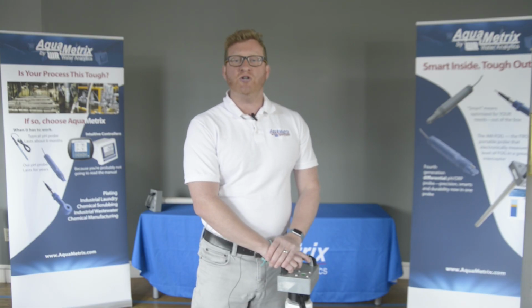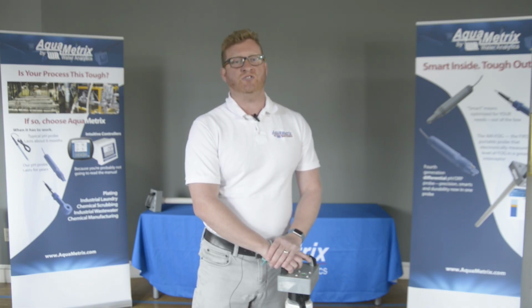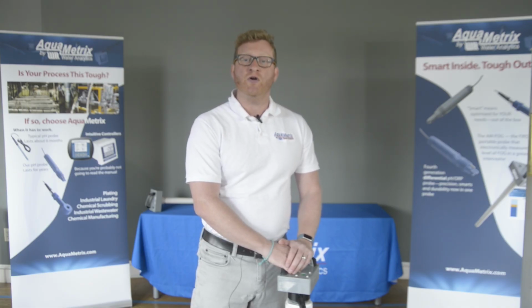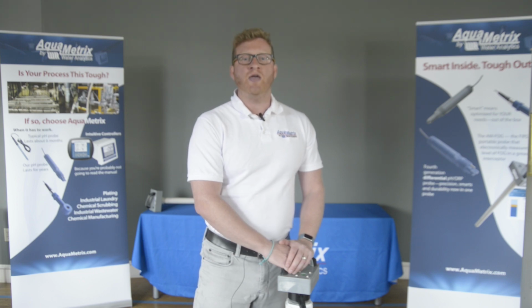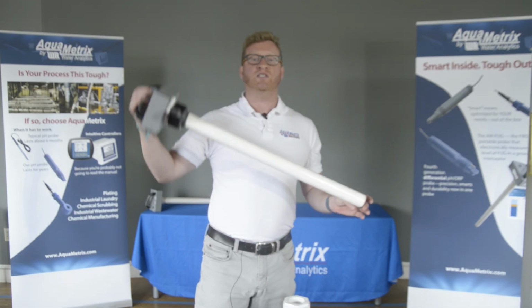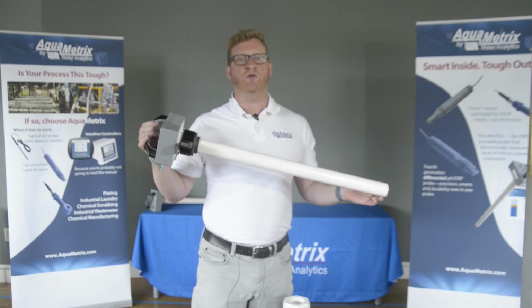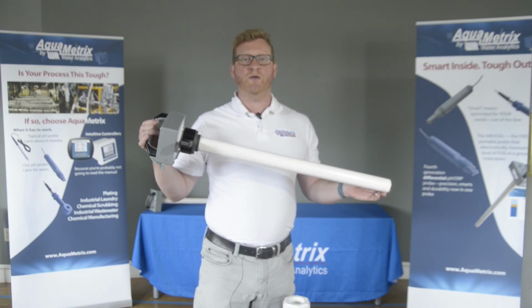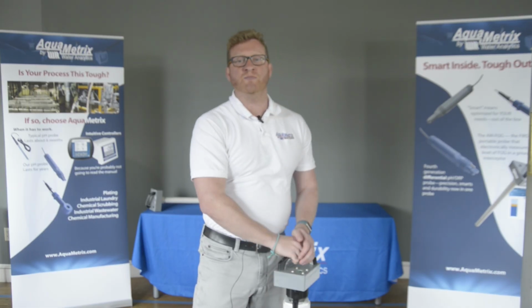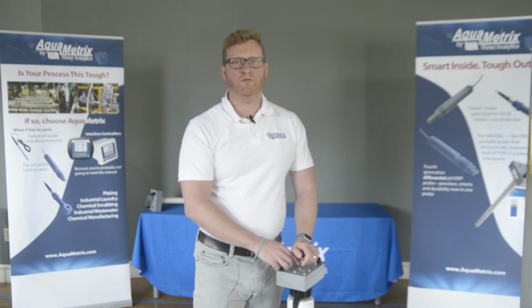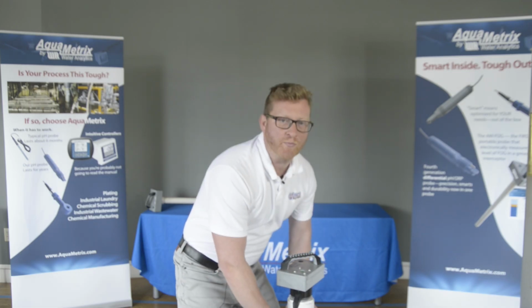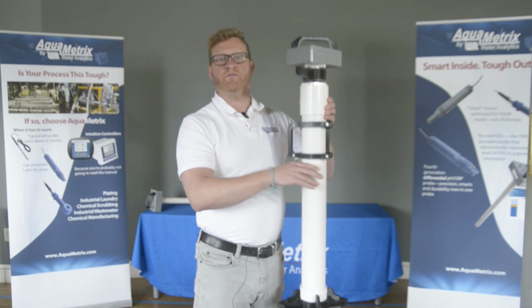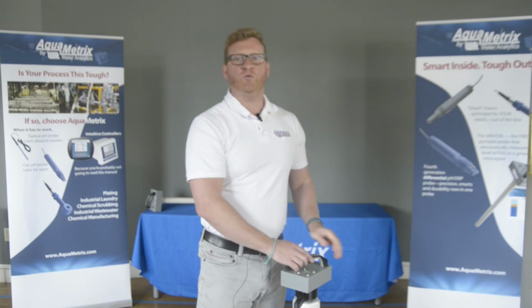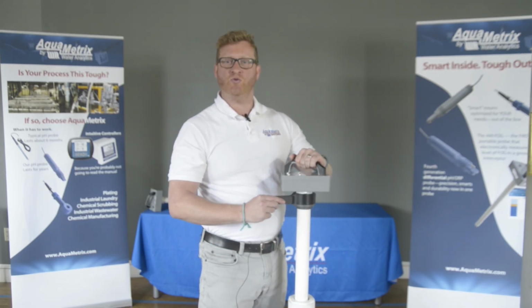It can electronically measure and record a fog level of any interceptor with a fog thickness up to 64 inches. How does it work? Well, the AM-Fog comes in sizes from 16 to 64 inches in increments of 8 inches. This one here is 24 inches and is sized for a typical hydromechanical grease trap found under a small restaurant. The probe measures capacitance on the surrounding medium and is minimally affected by the coating of the tube. When not in use, the probe is stored inside this hard PVC case. That's a secret second function, but more about that in a minute. Between the case and the probe is a squeegee that you can use to wipe off the probe.